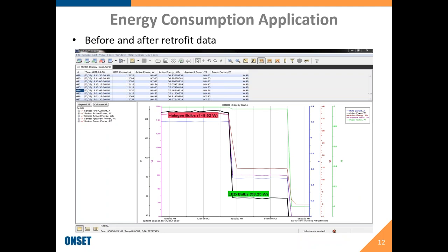We installed one of the plug load loggers and monitored during the day that we switched the lamps to new LED bulbs. As you can see, there was a pretty dramatic drop-off in the energy usage on that day. The line decreases sharply, and having a graph like this from a plug load logger can really prove the point quickly to a client or customer whom you're trying to show the efficacy of the changes that you make in their building.